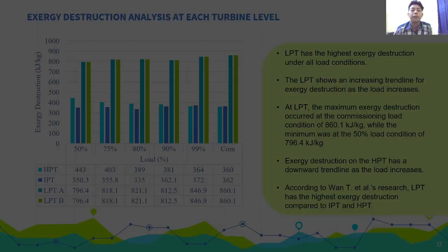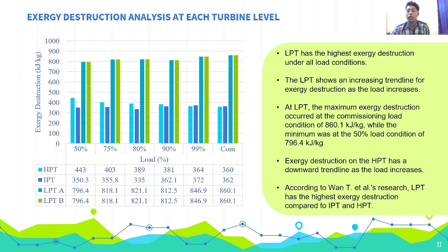This is an exergy destruction analysis at each turbine level. The low pressure turbine has the highest exergy destruction under all load conditions. The low pressure turbine shows an increasing trend line for exergy destruction as the load increases. At the low pressure turbine, the maximum exergy destruction occurs at the commissioning load condition of 860.1 kJ per kilogram, while the minimum was at the 50% load condition of 796.4 kJ per kilogram. Exergy destruction on the high pressure turbine has a downward trend line as the load increases. According to Wan T. et al. research, the low pressure turbine has the highest exergy destruction compared to the intermediate pressure turbine and high pressure turbine.